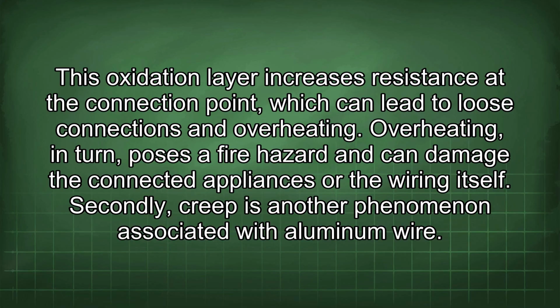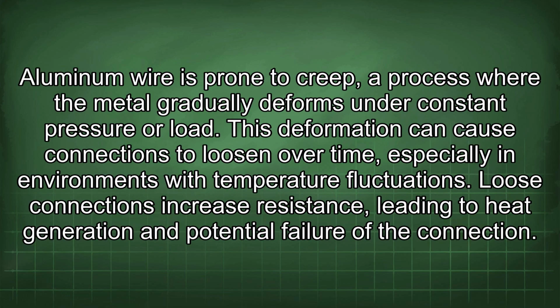Secondly, creep is another phenomenon associated with aluminum wire. Aluminum wire is prone to creep, a process where the metal gradually deforms under constant pressure or load. This deformation can cause connections to loosen over time, especially in environments with temperature fluctuations. Loose connections increase resistance, leading to heat generation and potential failure of the connection.